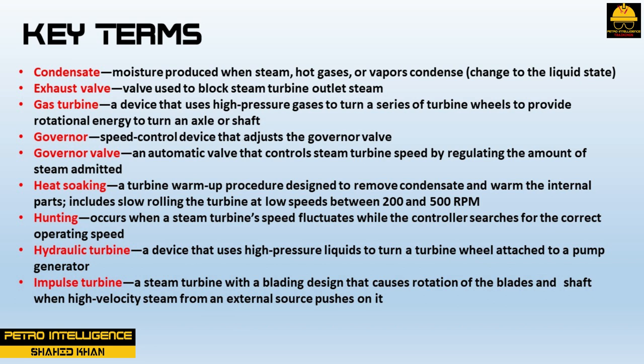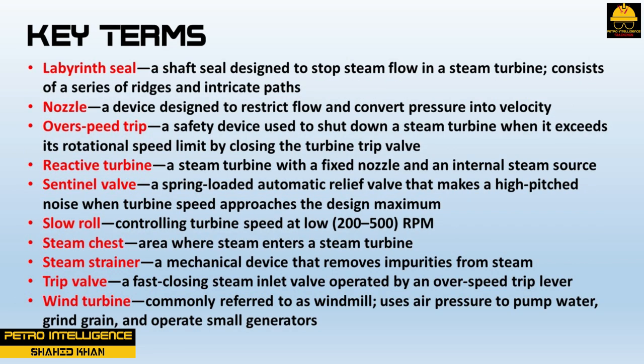Hunting occurs when a steam turbine speed fluctuates while the controller searches for the correct operating speed. Hydraulic turbine is a device that uses high pressure liquids to turn a turbine wheel attached to a pump generator. Impulse turbine is a steam turbine with a blading design that causes rotation of the blades and shaft when high velocity steam from an external source pushes on it. Labyrinth seal is a shaft seal designed to stop steam flow in a steam turbine, consisting of a series of ridges and intricate paths. Nozzle is a device designed to restrict flow and convert pressure into velocity.